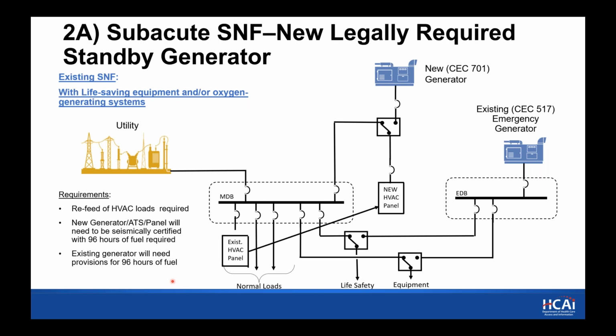Again, this is simple. Basically, if it's a subacute, it would be the same approach. New generator, new transfer switch, new panel, you transfer the HVAC loads to the new panel. And if there are some life safety equipment that's not on emergency, you would need to transfer that over. Again, the new generator, transfer switch, all the equipment would need to be seismically certified. The new generator would need to have fuel for 96 hours, and the existing generator would need to have fuel for 96 hours. Jamie, I have a question on the previous slide here.